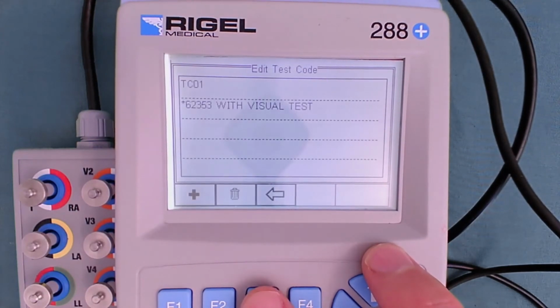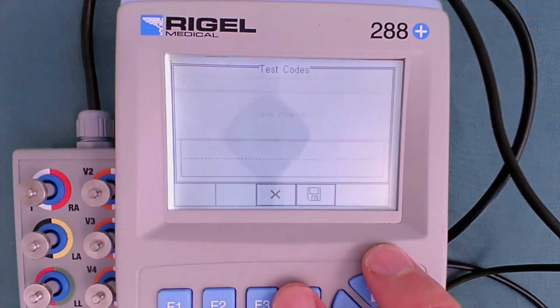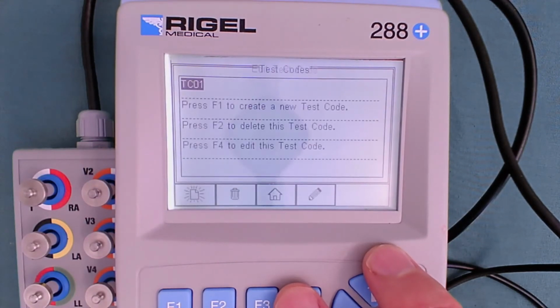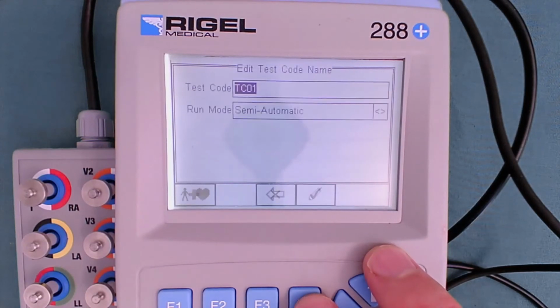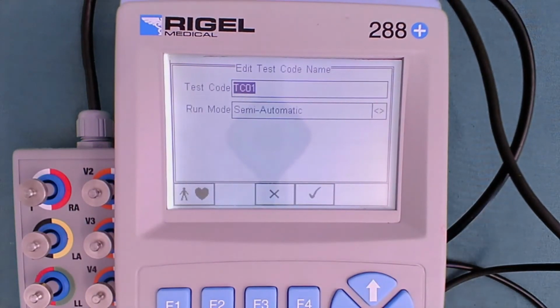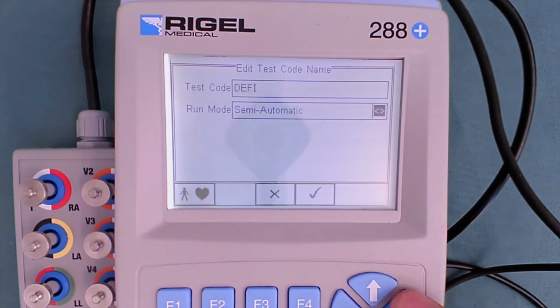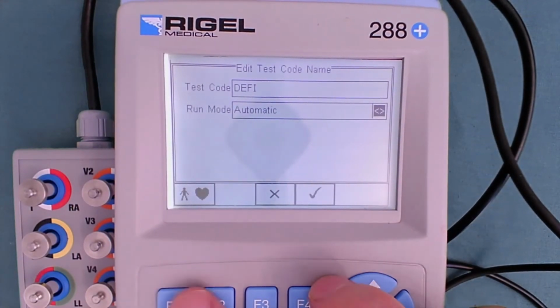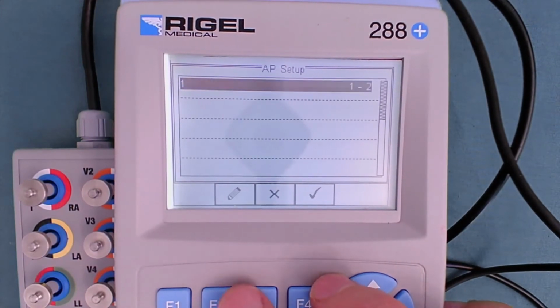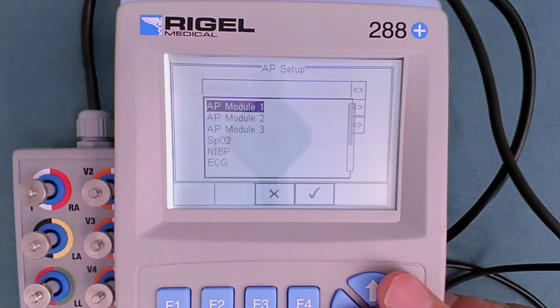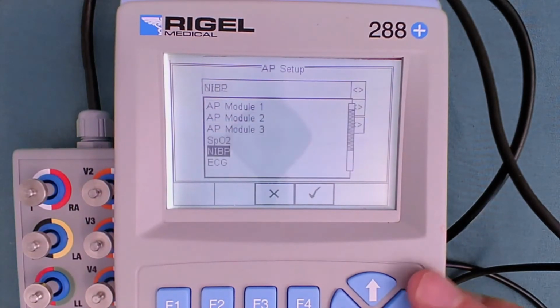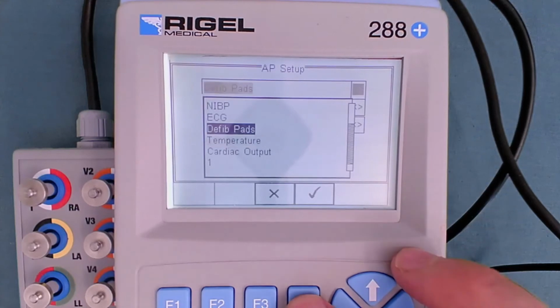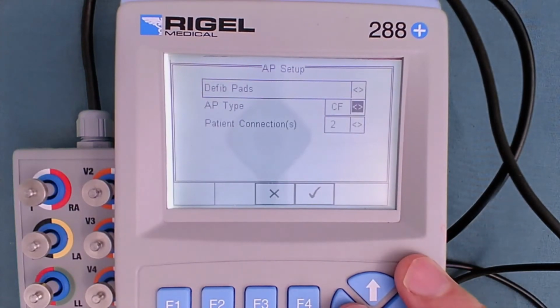We've got a new test code. And I didn't highlight this in the presentation. It's really useful. So if you can edit the name, you can only put a 4-digit code in, maximum 4 digits. For demonstration purposes, let's do it for DFib, DEFI. Make it an automatic test, and then we can press F1 to change our applied parts. Now for a typical DFib, we're going to have 2 patient pads, DFib pads, perhaps BF classification. So we'll select BF, 2 patient connections for each pad.